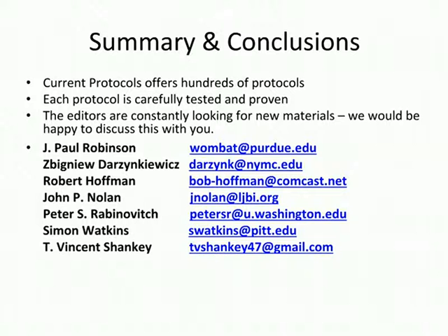Question: is there a specific protocol I can follow to calibrate using Q and B, independent of the manufacturer? John: yes, that's described in the Current Protocols unit by Bob Hoffman on calibrating your flow cytometer. It has a very detailed description of how to do it — making the measurements and then doing some intermediate-level Excel spreadsheet work to extract Q and B. You should be able to do that yourself by following the protocol, and Bob or I would be happy to answer any questions — our emails are available online.